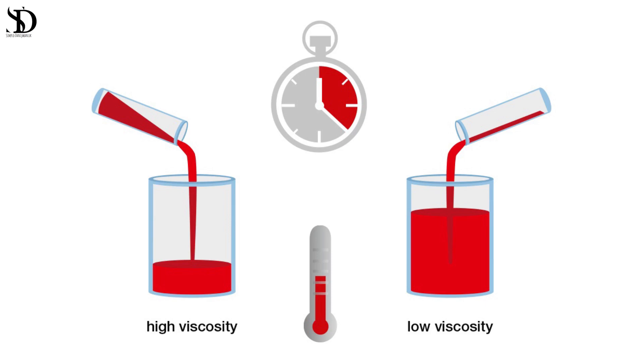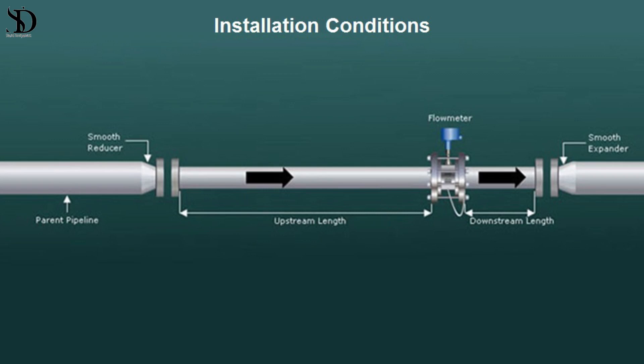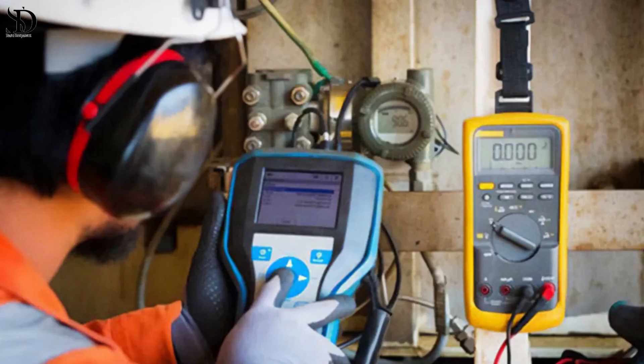Factors affecting flow measurement. Fluid properties — viscosity, density, and temperature — can significantly impact flow measurements. Installation conditions: accurate measurement often depends on proper installation, including the location of the flow meter, pipe size, and straight pipe runs upstream and downstream of the meter. Regular maintenance and calibration are crucial to ensure accuracy and reliability.